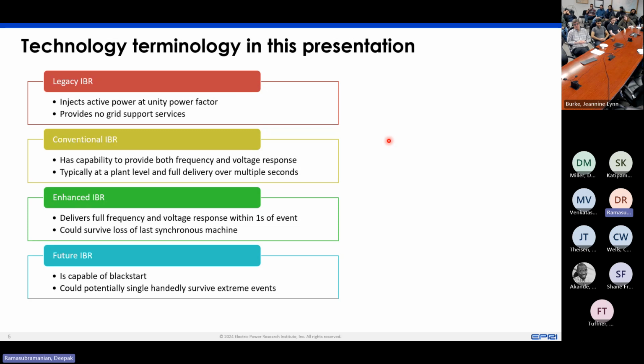So we started coming up with four categories, or four subsets, going purely by the amount of services these resources provide to the network. First, you have legacy inverters—the initial, quintessential 20-years-ago inverter-based resource that operated at unity power factor and provided no grid support services. Then you come to the conventional inverter, which does provide frequency and voltage response, but typically over multiple seconds, at a slower pace, and at a plant level.